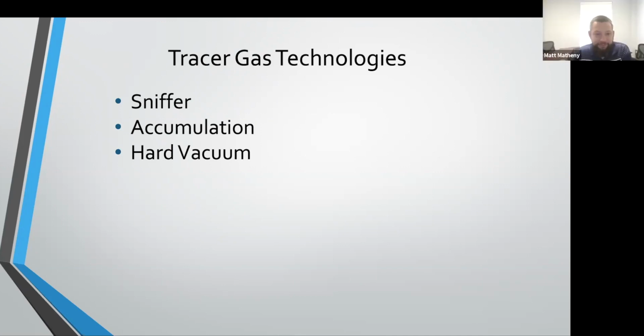So next is hard vacuum. Tell us about that. Yeah, that's the cream of the crop. If you want absolute certainty that your part's leaking above a set leak rate or not, it's also the ultimate in sensitivity. When we get into tracer gas leak detection, we often have to, for the application, describe the leak rate we're looking for in scientific notation because there are so many zeros after the decimal point. So if you hear someone who's got a lot of experience with tracer gas leak detection, they'll talk in decades. So they'll say a -5 leak, -6 leak, a -10 leak.